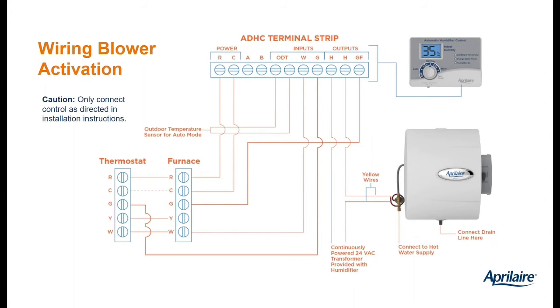Then at the humidistat, you see we got a GF. We're going to add another wire, and that's going to go from GF, F is for furnace, GF to G on the furnace, and that's it. So all you've done, basically, is create a G circuit from the thermostat to the humidistat, and from the humidistat to the furnace. That's it, you're done. Internally, we call that breaking the G. But the concept is that it lets the humidistat know when the thermostat calls for fan. When the thermostat calls for fan, the humidistat knows it, and it can tell the humidifier to run. And then, of course, it can pass that fan call back to the furnace so the blower actually runs.